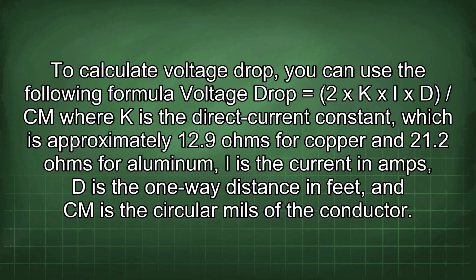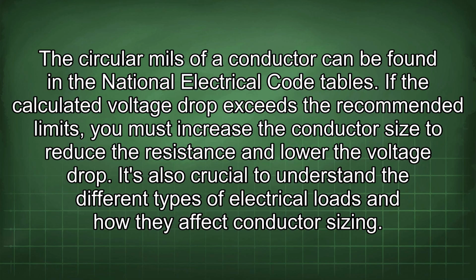2 x K x I x D / CM, where K is the direct current constant, which is approximately 12.9 ohms for copper and 21.2 ohms for aluminum, I is the current in amps, D is the one-way distance in feet, and CM is the circular mils of the conductor. The circular mils of a conductor can be found in the National Electrical Code tables. If the calculated voltage drop exceeds the recommended limits, you must increase the conductor size to reduce the resistance and lower the voltage drop.